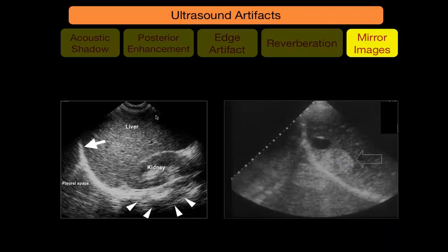Mirror image artifact — a duplication of an image appears along a highly reflective structure like the diaphragm. The sound wave hits the diaphragm, rolls around it, and returns after a time delay. The machine interprets that delay as another structure in the deeper field — so you may see another liver, another kidney, or another hepatic lesion in that area. That is all, and thank you very much.